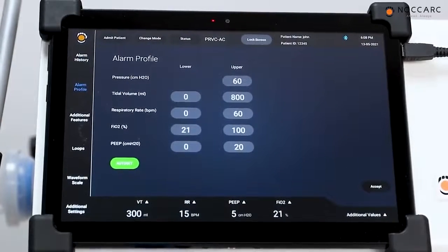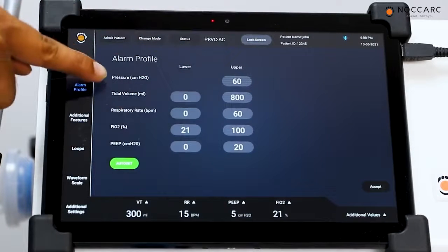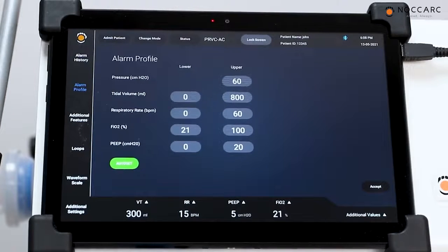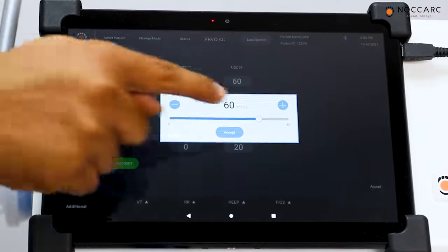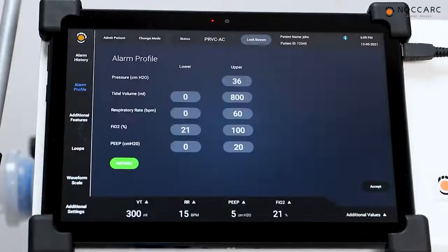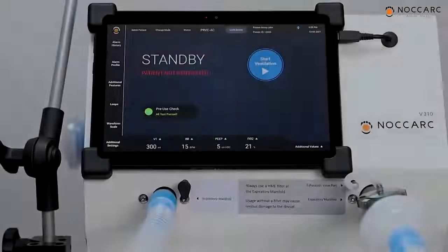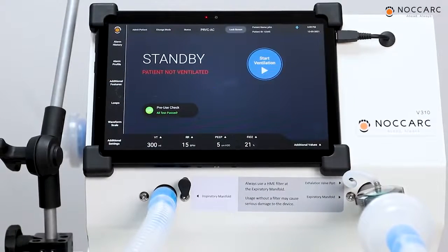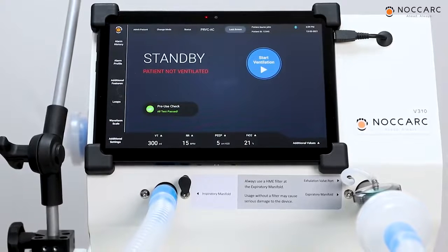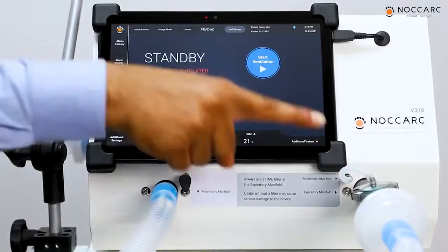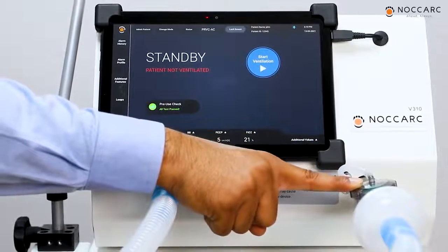When user wants to set PRVC mode, it may be PRVC CMV, PRVC AC or PRVC SIMV, always ensure you have set upper limit for pressure. To set this value, press on this particular parameter and change the value. This value should be as per patient's requirement. Press on accept. When user wants to use Noccarc V310 in any invasive or non-invasive ventilation mode, always ensure the active exhalation valve is plugged in expiratory port.